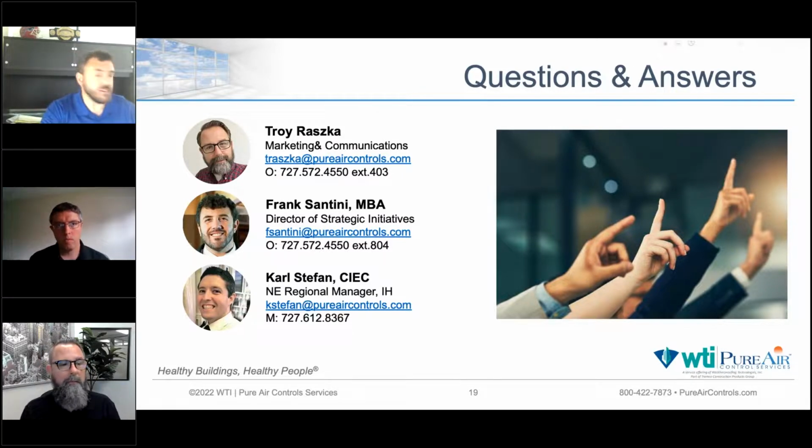Go ahead, Karl, if you want to say anything. Right, I would say certainly air handlers. I've worked with numerous clients that, if the Joint Commission starts opening up these air handlers to take a look, it could be some serious trouble if they see basic signs of accumulation and fouling, regardless of your final filters. So yeah, they will look at your air handlers. Yeah, that's good information.